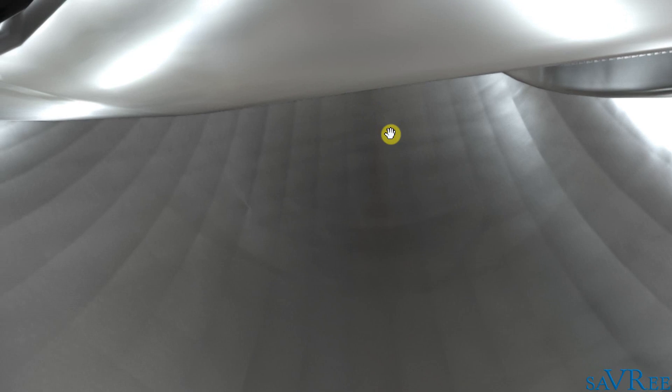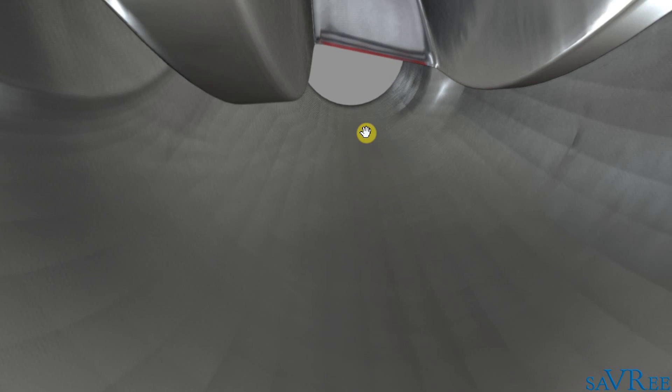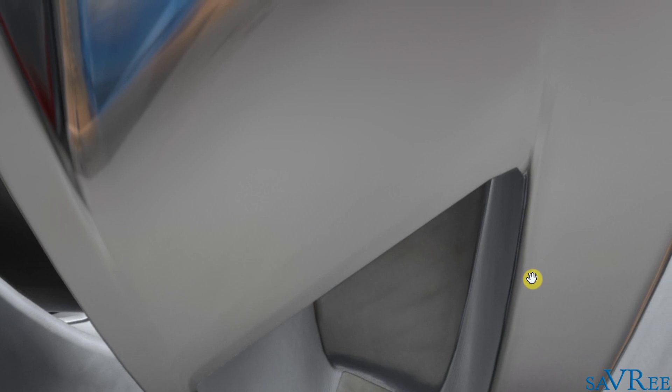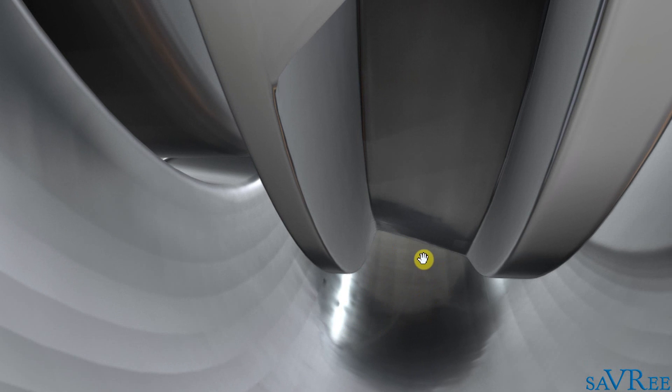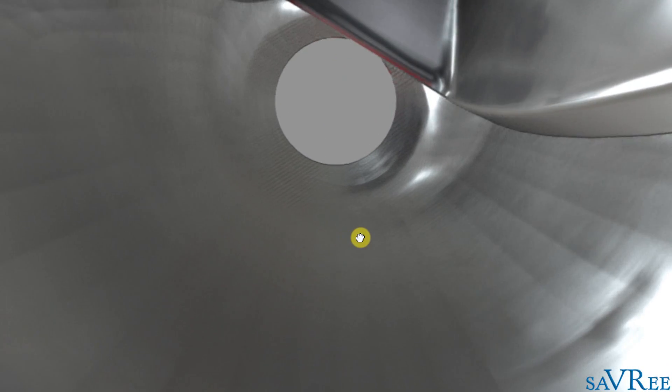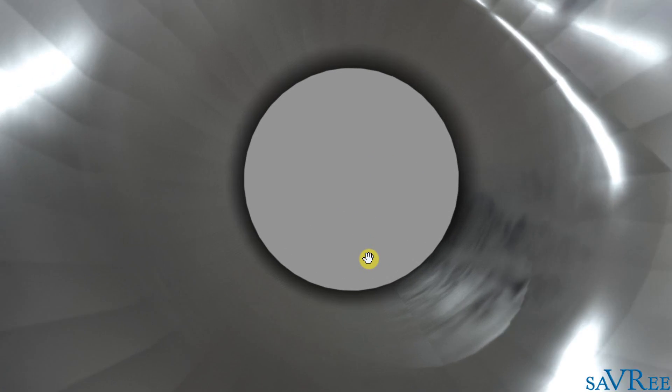And then we're going to exit the impeller and go to the volute casing. Now we're inside of the volute casing. And look, as we are thrown out of the impeller, we enter the volute casing. And notice how much more space there is as we move towards the discharge pipe. That's this pipe that we can view at the top of the screen. Compared to how much space there is on the opposite side. You can see it's getting continually narrower if we want it to flow back the other way. So down this side here is quite narrow. The diameter of the volute casing is gradually increasing until we get onto this side here. And that means our flow path is gradually getting bigger. And all of a sudden we've got loads of space. And that means the velocity is decreased and the pressure is increased. And then we can move on our way through the rest of the system.